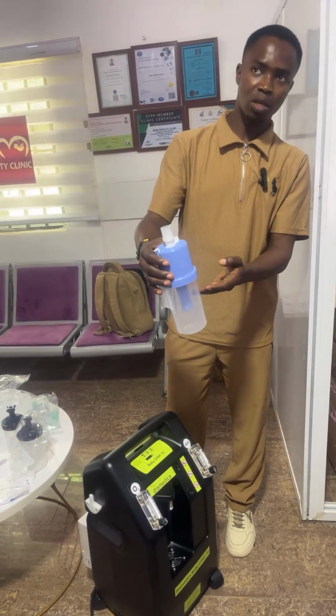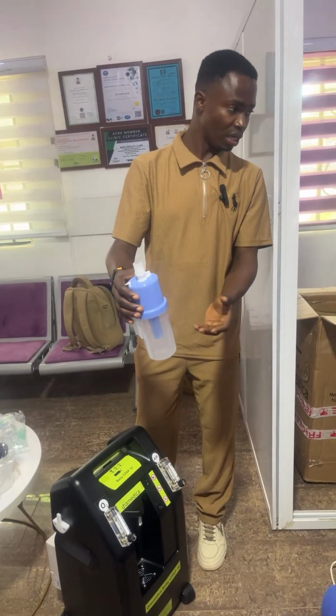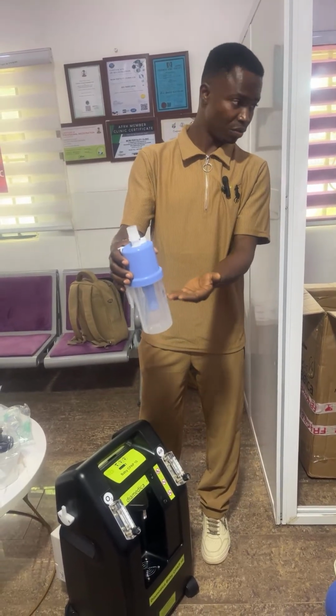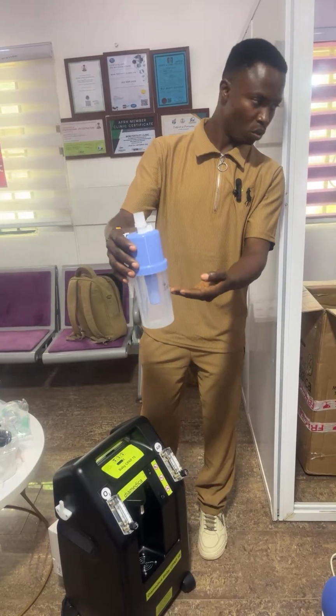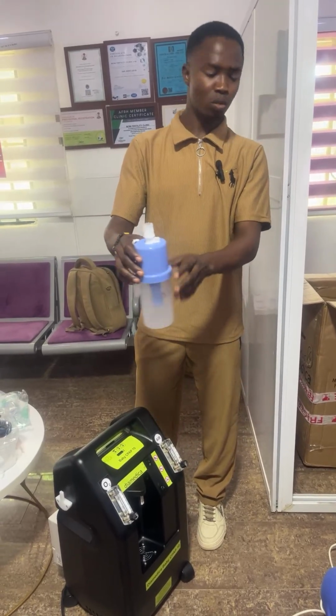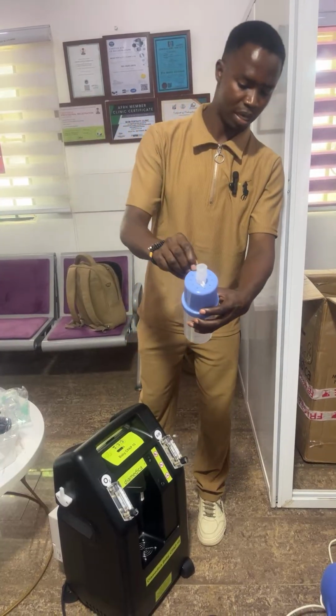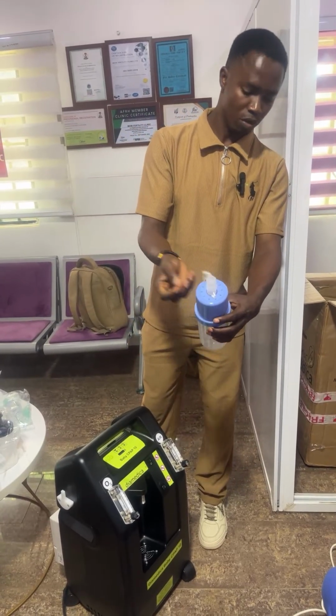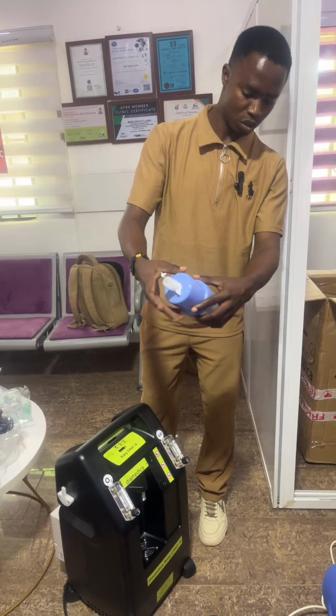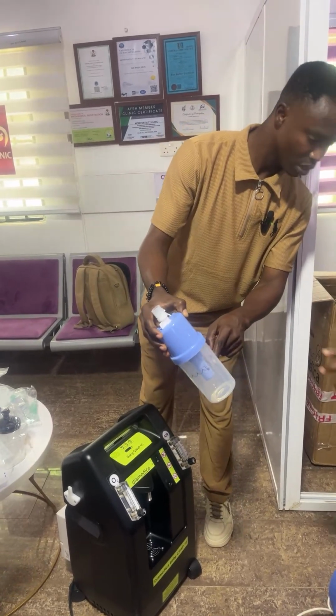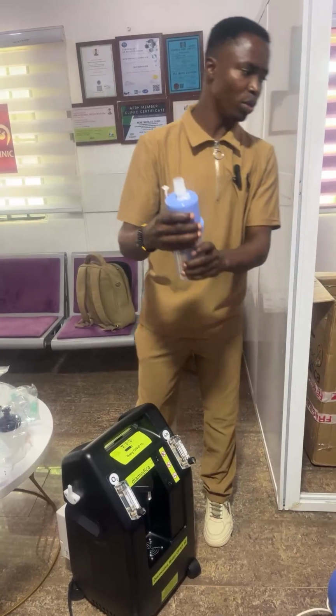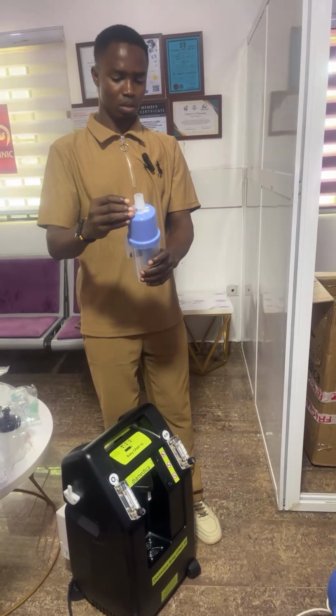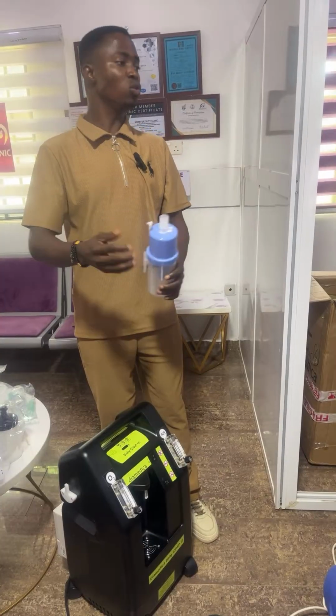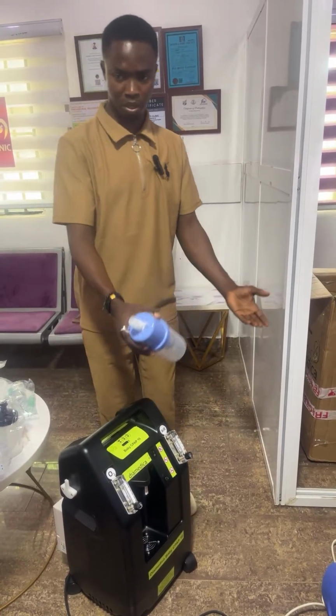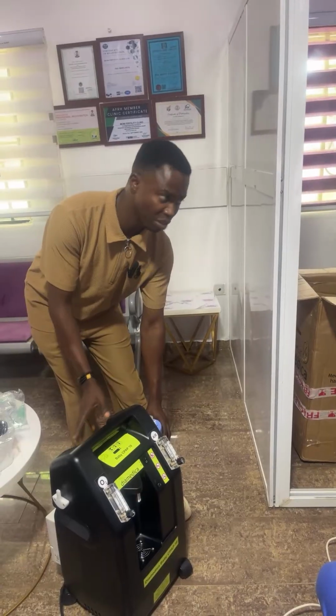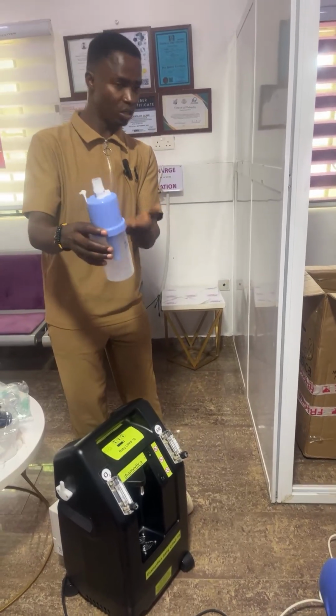You check, it does not reduce quickly, let's say in 5 or 6 hours before you can even reduce at all. But if it goes down or above, you don't need to switch off the machine. You have this here, just open. If you have a longer syringe, or even a short one, you can see it extends to this place. No, this has to be locked. Yes, that means when you are using the machine on a baby, you don't need to switch off the machine to adjust it or to fill it up.